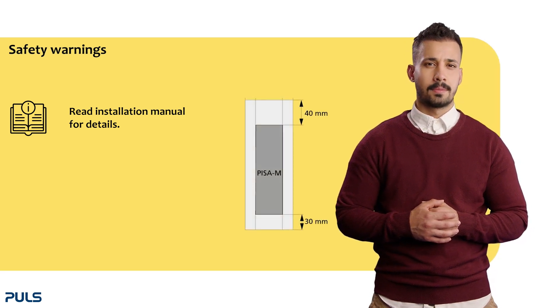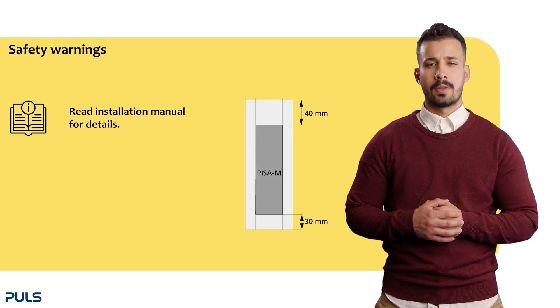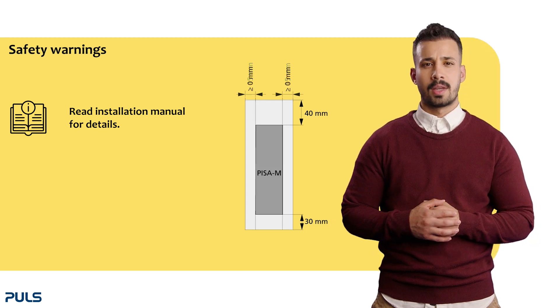When setting up the PISA-M, minimum installation clearances of 40mm on top and 30mm on the bottom are needed. In case the adjacent device is a heat source, you need 15mm lateral clearances. Between multiple PZN modules, no clearance is needed.